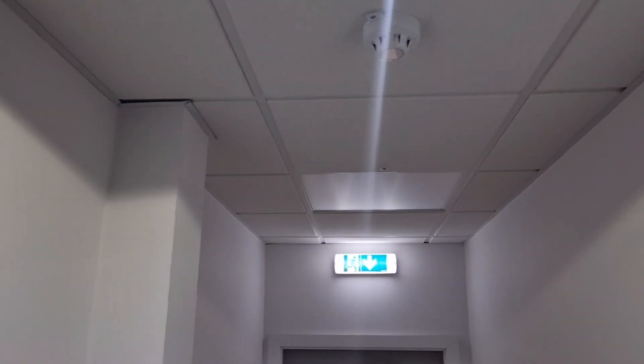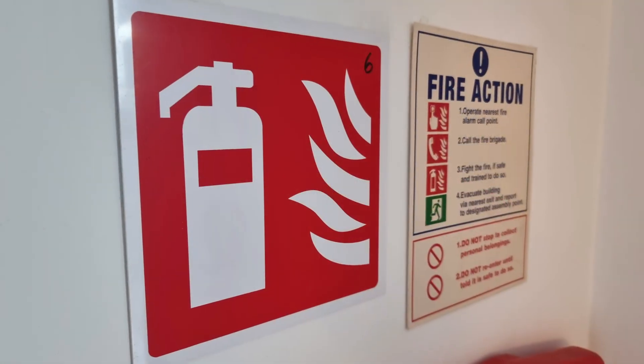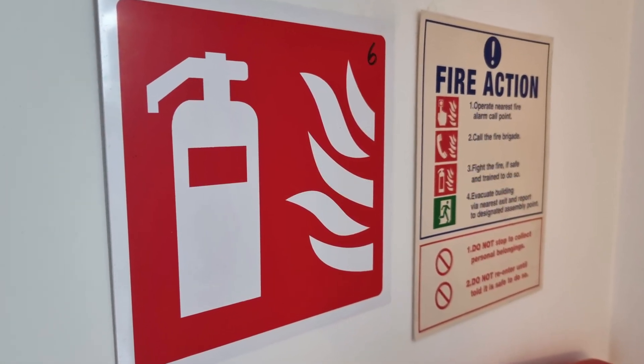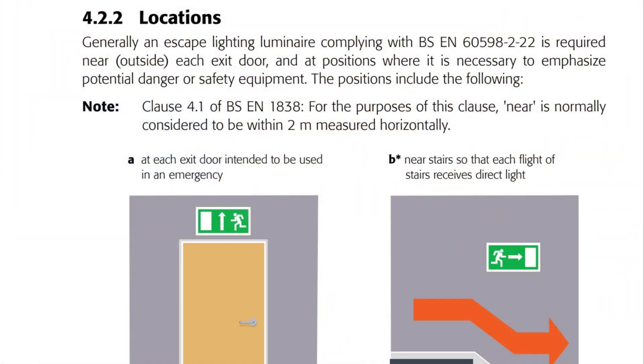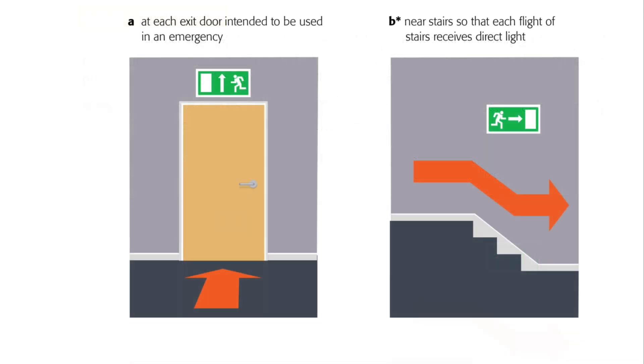While you won't necessarily install signs that aren't a luminaire, some signage will be incorporated into your emergency fittings, and signs that aren't luminaires still require a certain level of illumination on them. The guide then identifies locations where escape lighting luminaires will be required, under subheading 4.2.2. These positions include at each exit door intended to be used in an emergency.